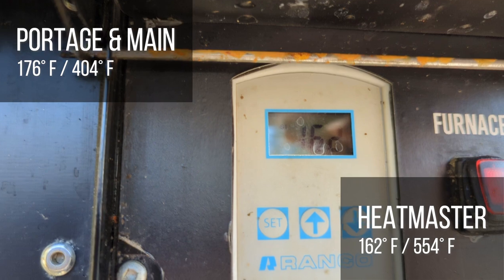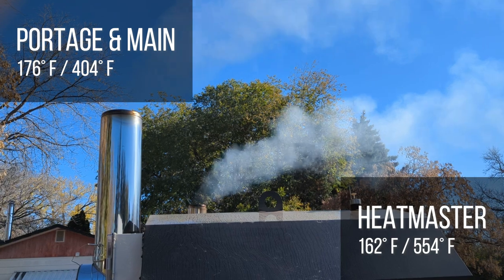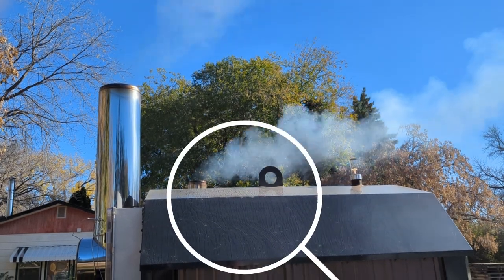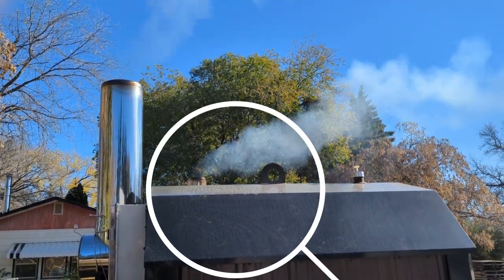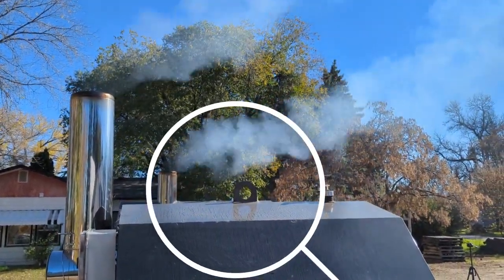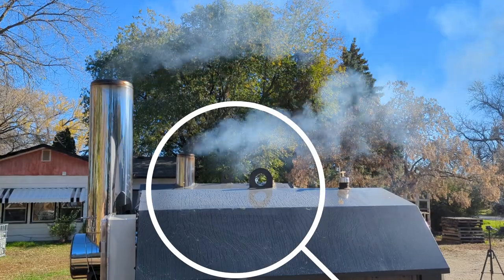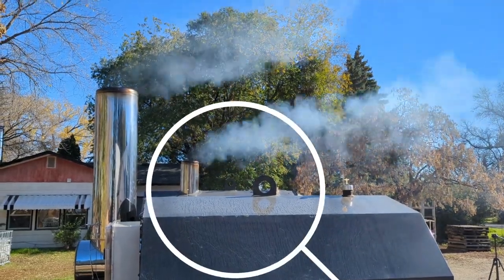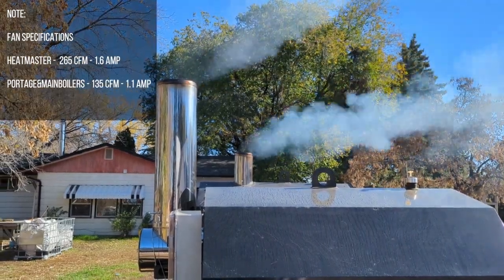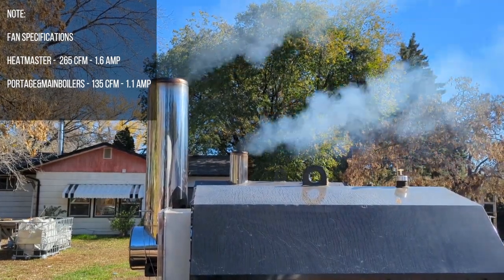We're thinking of unplugging one heat exchanger on both of them to keep the test fair. We've been burning for about half an hour now with a fresh load of tamarack at 15–30% moisture — both boilers received the same moisture content and same weight of wood. You can see the smoke coming out of each unit. The Heatmaster has higher velocity and is blowing a bit more air through, which our air meter test confirmed.